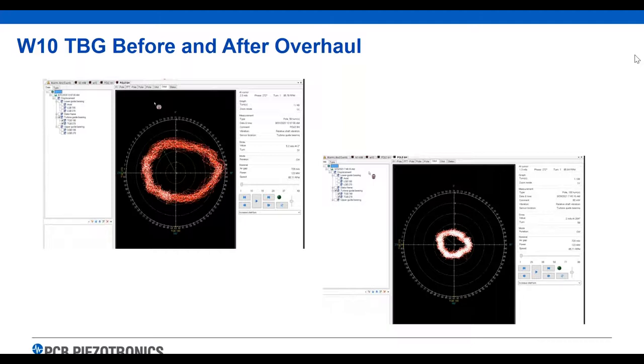That oil head challenge was for a new unit and it was a head scratcher — it took us quite a while to find what was causing that oil head vibration. The tri-axial accelerometers provided great data for us to isolate the problem. We use the accelerometers in combination with displacement probes to really hone in on where the trouble was coming from. We've used accelerometers on commissioning units as well — new generator, new turbine — to monitor vibration or acceleration at specific points to make sure our new units are performing as we expect.